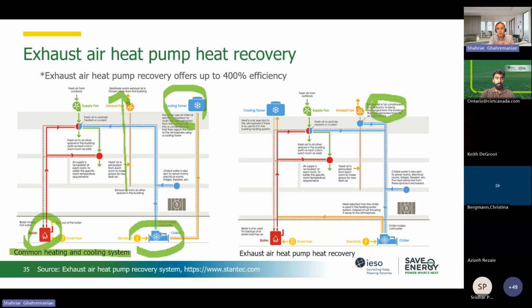Maybe the piping diagram that we have, it means that it goes to the sources of the cooling. But if you have a heat recovery chiller, then you are right. So we don't need that conditioning up there. Then a heat recovery chiller can take advantage of that one. Yeah, either of them: either putting a heat pump up there and then taking it down and bringing it to the chilled water distribution that you have, or as you said, install a heat recovery chiller and then take the heat to the heat recovery chiller and use that one. Either of these applications.